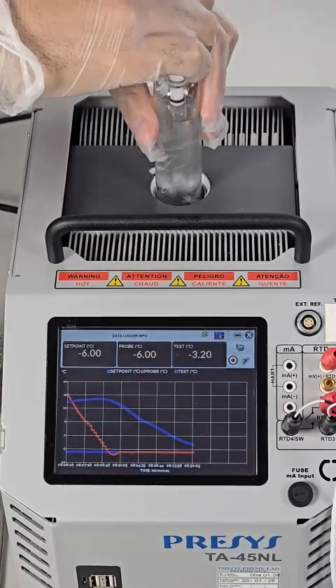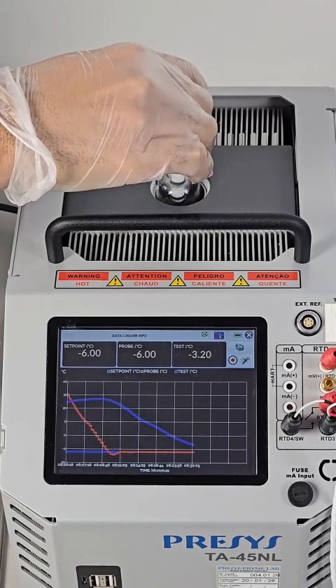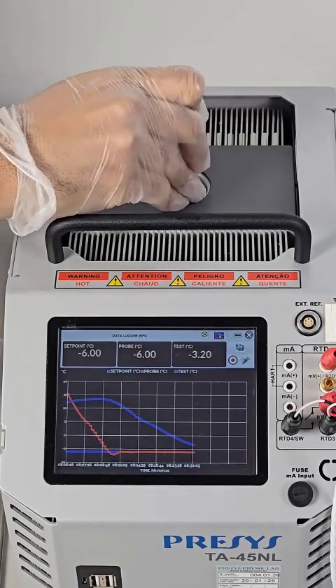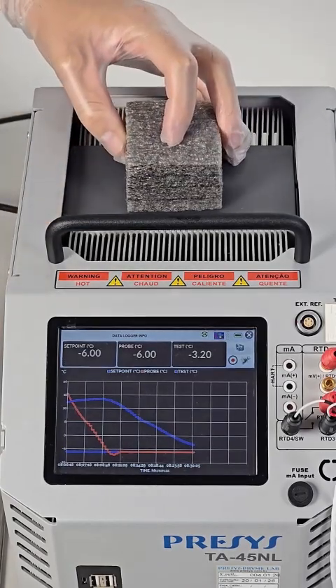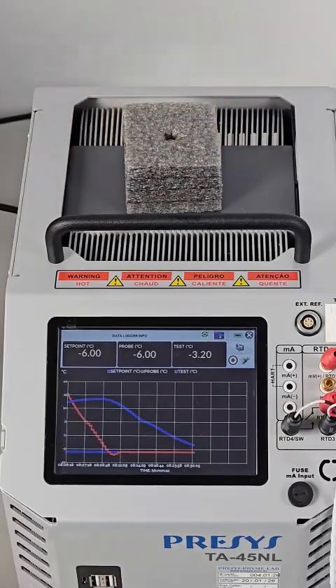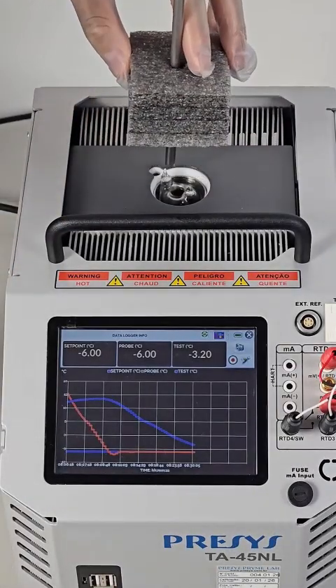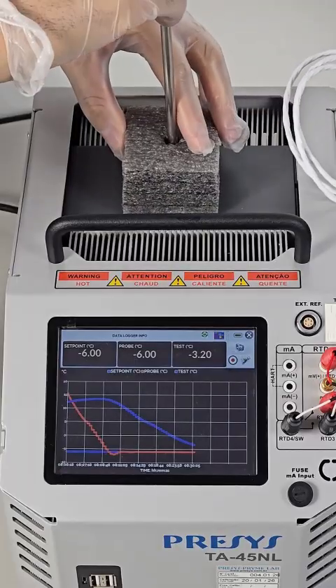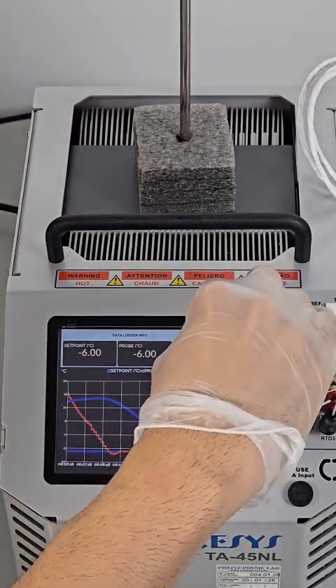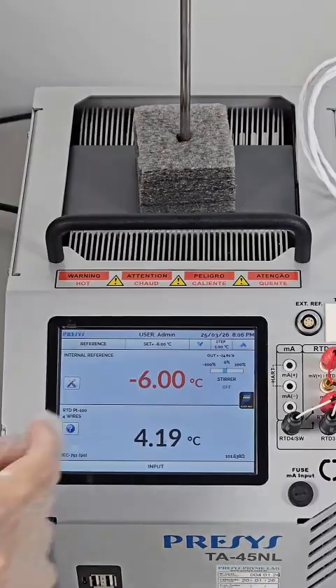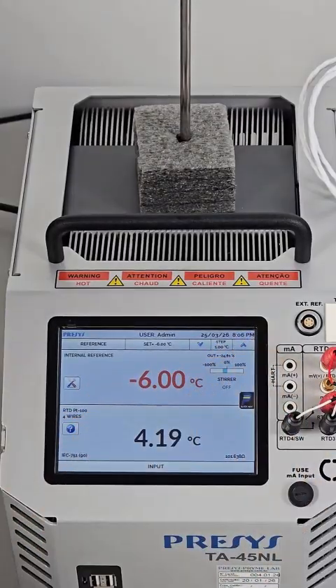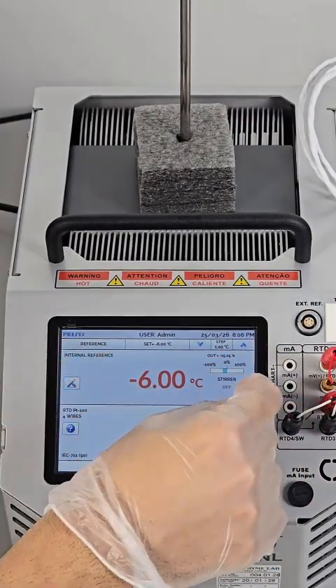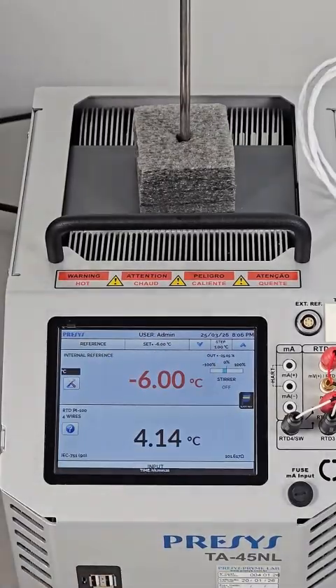Carefully observe the interior of the cell during this procedure. Gradually, a descending frozen region will become visible, forming from top to bottom along the inner wall. This visual phenomenon indicates that equilibrium between phases is being established. Maintain the set point at -6 degrees Celsius for approximately 8 minutes.